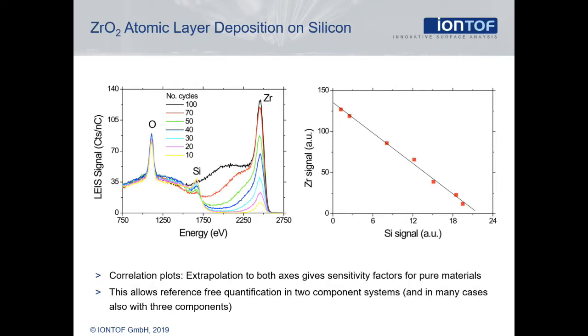This anticorrelation can be shown in many elemental combinations and is universal except for some known elements. Here is an example of zirconium oxide growth on silicon dioxide: the more zirconium is detected, the less silicon signal there is. Besides demonstrating the absence of matrix effects, these plots also have a practical use for quantification. When the straight line can be fit to a few data points, the intersection with the two axes shows the intensity for the pure material, yielding the sensitivity factor for each element. To draw the line, only a few samples with different ratios of the two elements are required — in particular, the pure material is not needed. With sufficient samples, this way of quantification can also be applied to three or more elements in the sample.